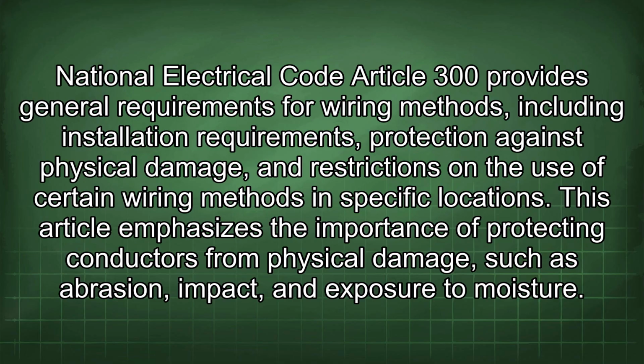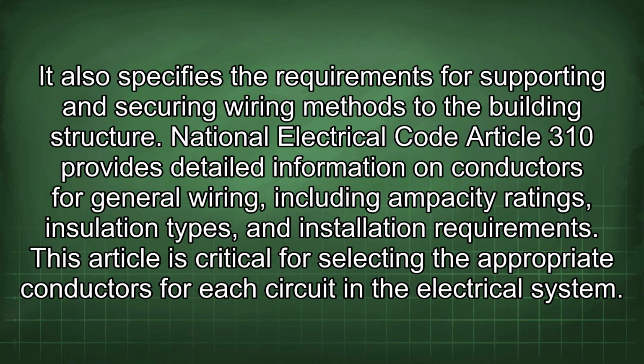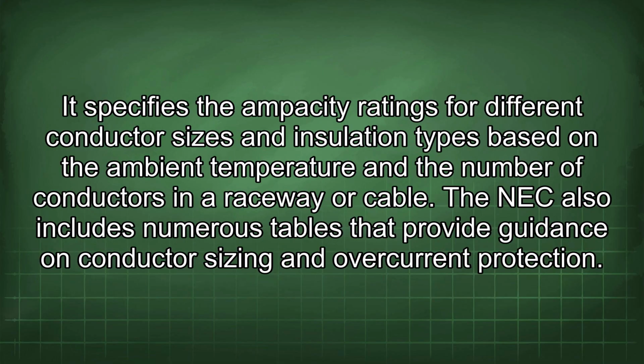National Electrical Code Article 300 provides general requirements for wiring methods, including installation requirements, protection against physical damage, and restrictions on the use of certain wiring methods in specific locations. This article emphasizes the importance of protecting conductors from physical damage, such as abrasion, impact, and exposure to moisture. It also specifies the requirements for supporting and securing wiring methods to the building structure. National Electrical Code Article 310 provides detailed information on conductors for general wiring, including ampacity ratings, insulation types, and installation requirements. This article is critical for selecting the appropriate conductors for each circuit in the electrical system. It specifies the ampacity ratings for different conductor sizes and insulation types based on the ambient temperature and the number of conductors in a raceway or cable.